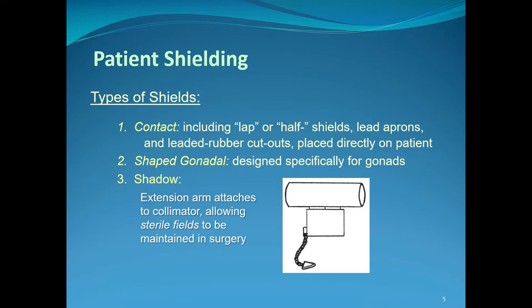Shadow shields hang off of the collimator box and don't touch the patient. One advantage is you can adjust the shadow shield to make the cast shadow larger or smaller. They also work well in sterile fields, like those encountered in surgical radiography. In general radiography suites, we're mostly talking about shaped gonadal shields and contact shields. Contact shields are designed to be used outside of the primary beam path, while shaped gonadal shields are designed to be placed over the gonads and shield them from the primary beam.